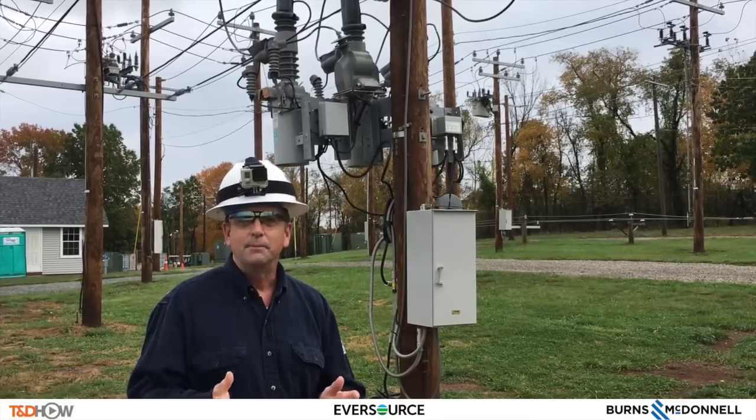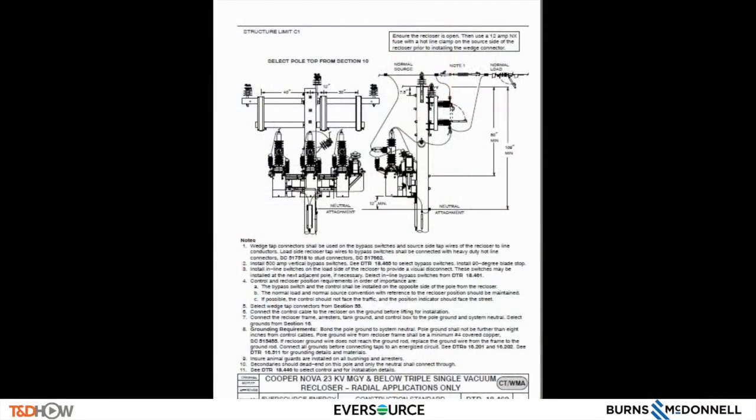This is the Cooper NOVA 23KV MGY below triple-single vacuum recloser, which is for radial applications only. It is denoted DTR 18.462. Some of the highlights of this DTR are the actual dimensions, depicted here. We have wedge tap connectors that will be used. We have the normal source, normal load. Some notes: no wedge tap connectors shall be used. Also mentioned are the 600 amp vertical bypass switch and the installation of the inline switches.